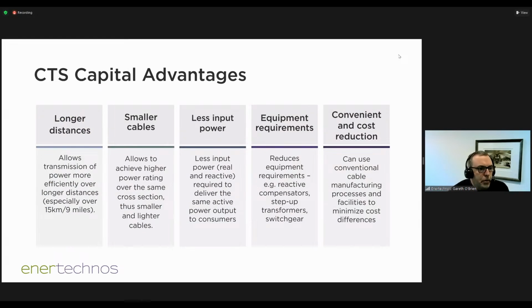Capital advantages in terms of putting the cable in. I won't read all of this because there isn't time, but basically it's able to go longer distances, able to go underground in situations where you might typically go overhead. It's harder and harder to get wayleaves and permissions for overhead. It takes longer, delays projects. Lower power input means you can go with smaller cables. You can reduce the size of step up, step down transformers in some scenarios. And you can either reduce the size of reactive compensators or sometimes do away with them completely. There's no capex typically required in the factory to manufacture the cable. It can be made on existing equipment.